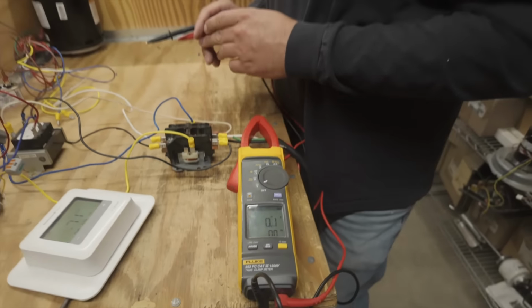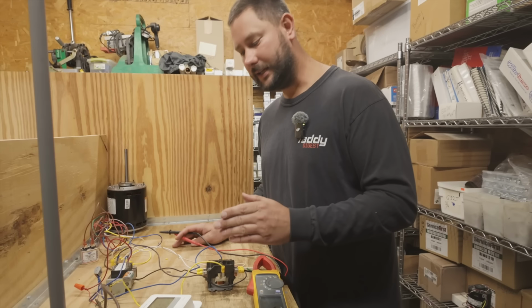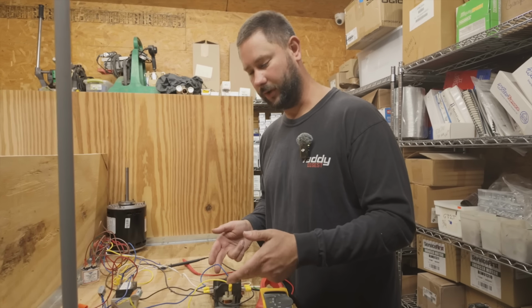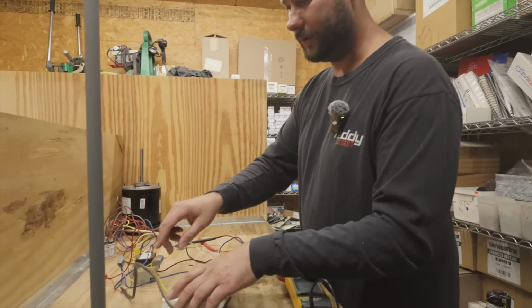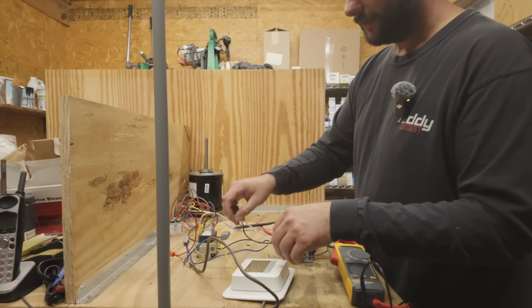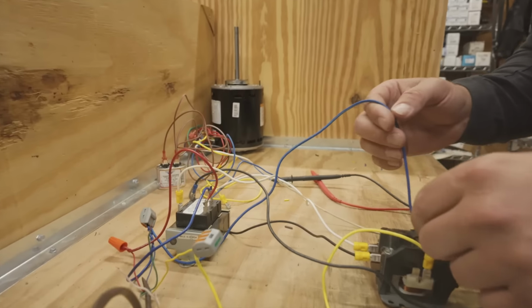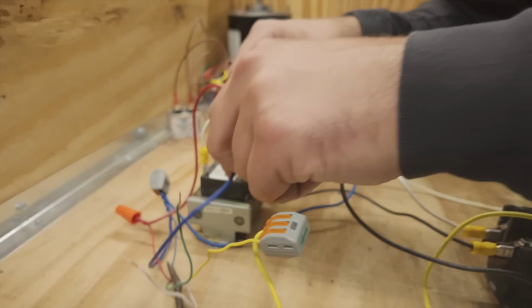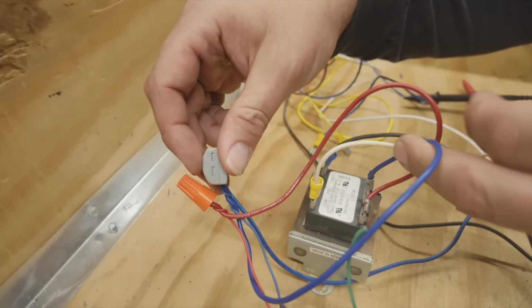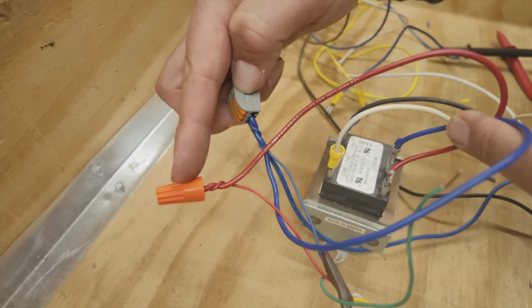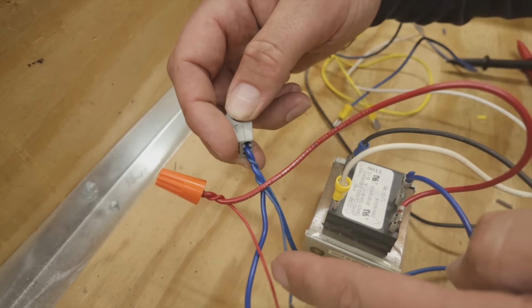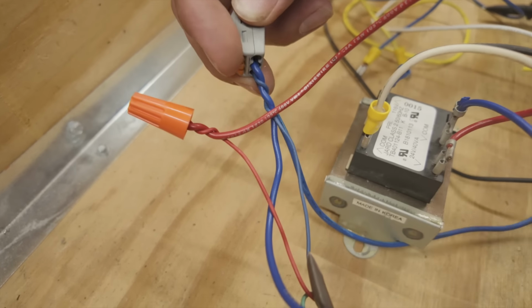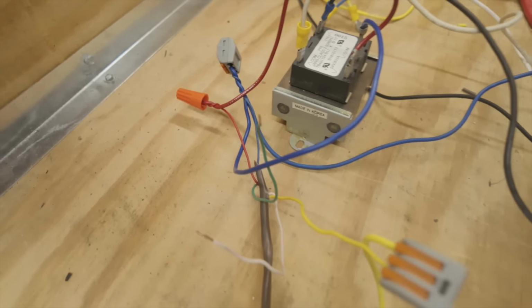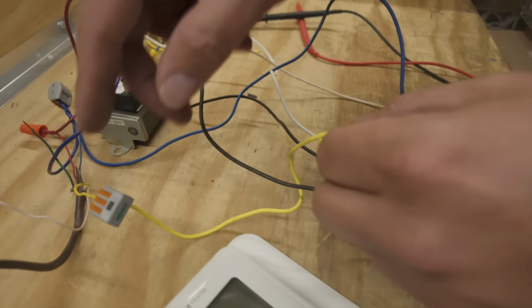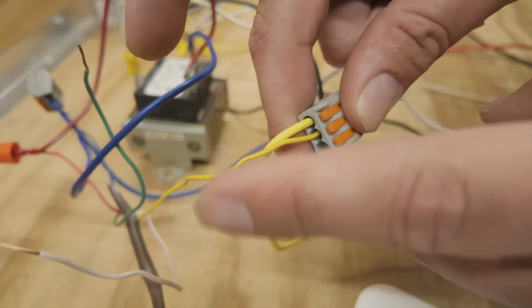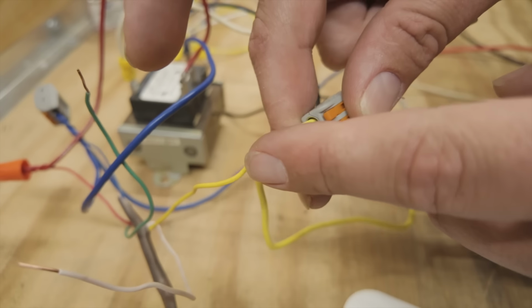All right, now to make this pull in, we've got to give a call to this coil. How do we do that? Well, you can see my thermostat wires. Where does this blue wire go? It goes to the transformer's common, one side of the 24 volts. See, we've got the common going to the thermostat. And then the yellow, which is the other side, goes to my yellow wire. It goes to my Y terminal on my thermostat.